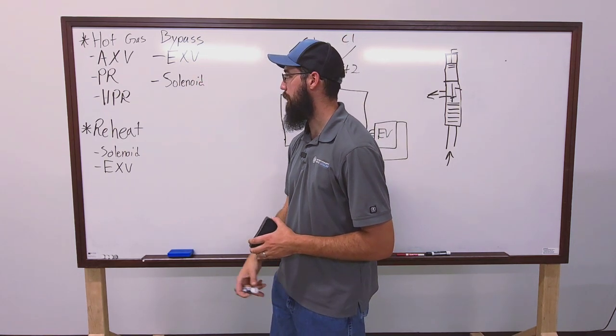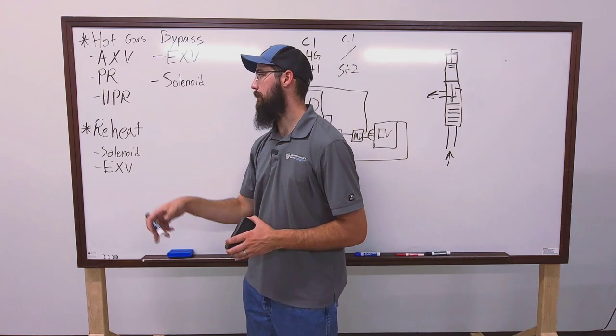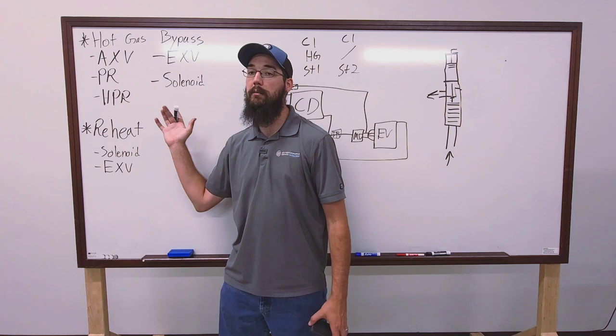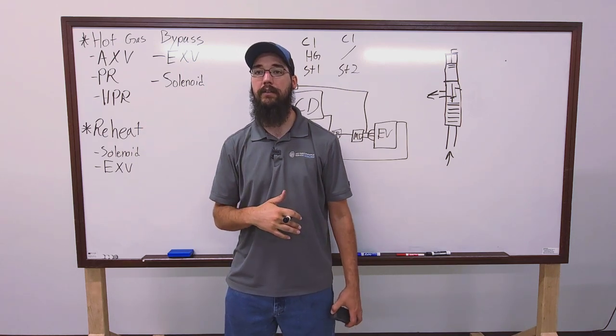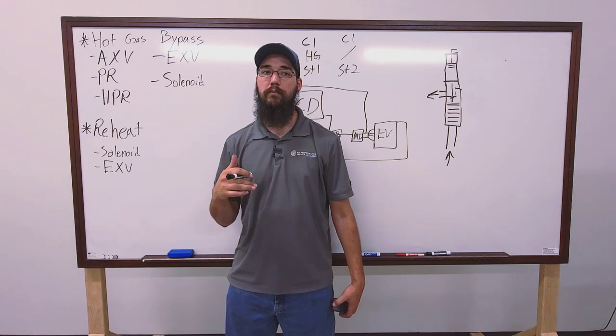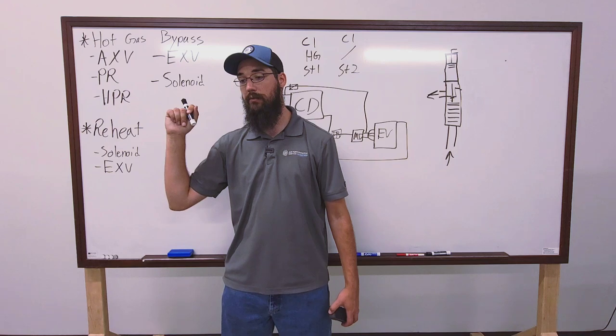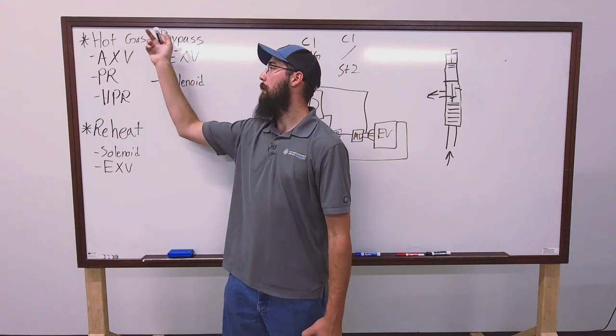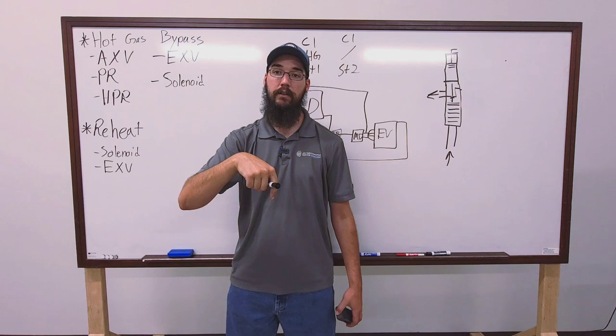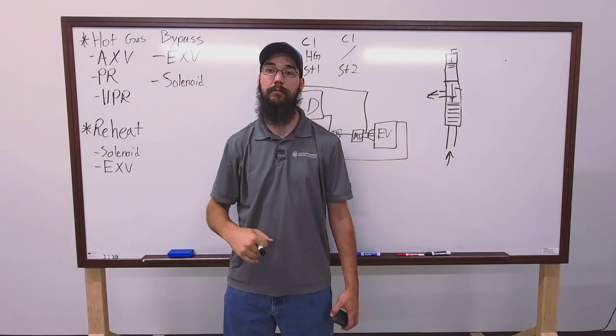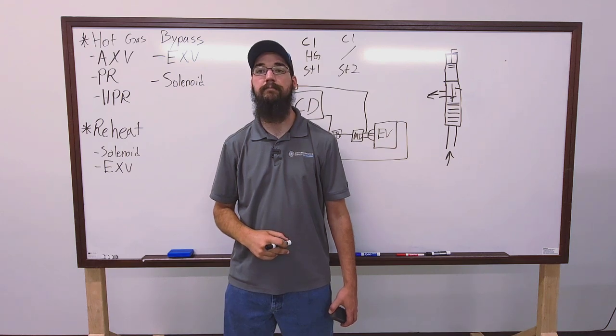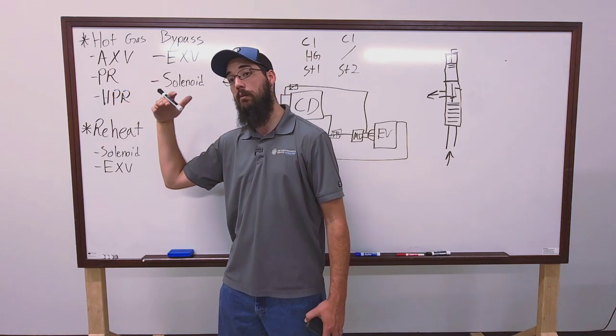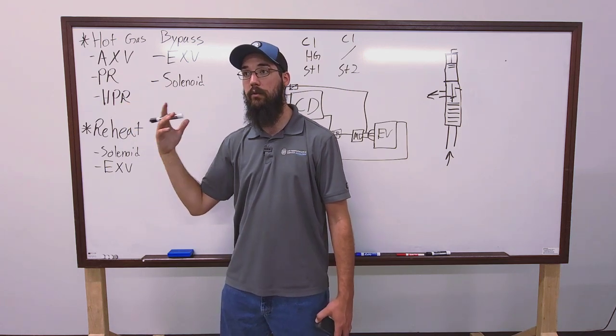So, this is a... I usually see these on more industrial... I'm trying to picture... It's been a long time since I actually have ran into one. Honestly. A lot of them, especially newer stuff, like I said, they're going to EXV based or they're just doing straight solenoids anymore. Head pressure regulating valves or control valves are honestly more low temp side. I did want to bring it up because they are a thing. They are part of a hot gas bypass. So, yeah. Typically, HPR valves will actually... They're regulating more of a head pressure.